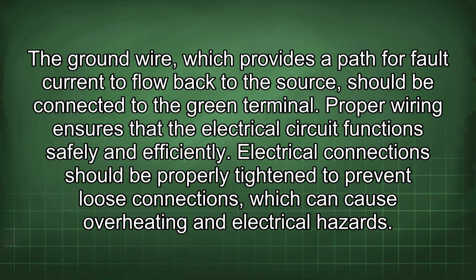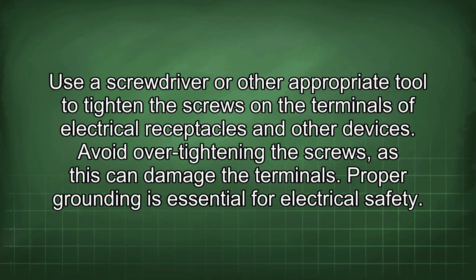Electrical connections should be properly tightened to prevent loose connections, which can cause overheating and electrical hazards. Use a screwdriver or other appropriate tool to tighten the screws on the terminals of electrical receptacles and other devices. Avoid over-tightening the screws, as this can damage the terminals.